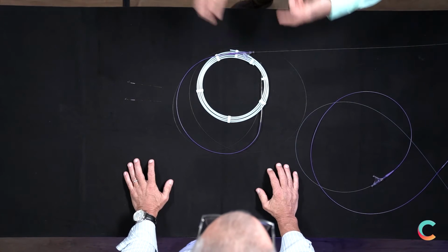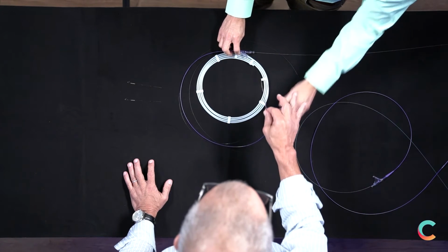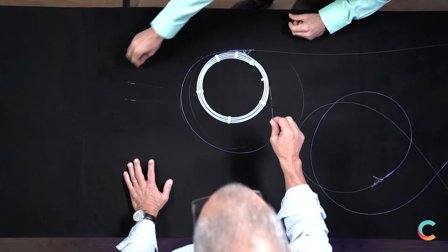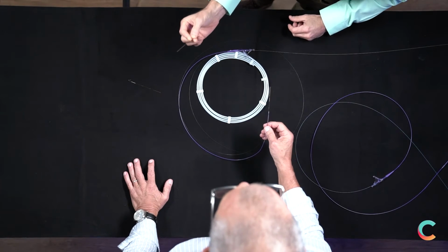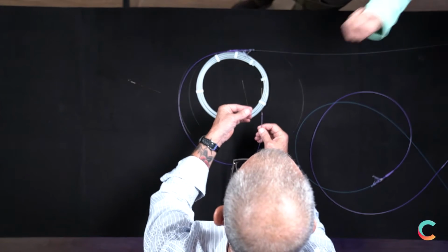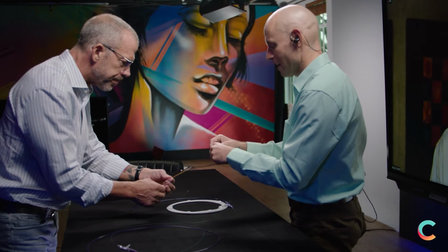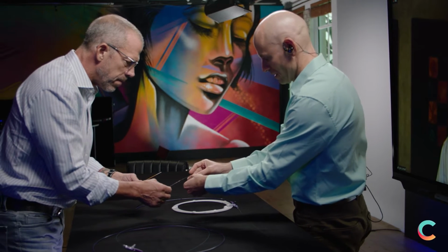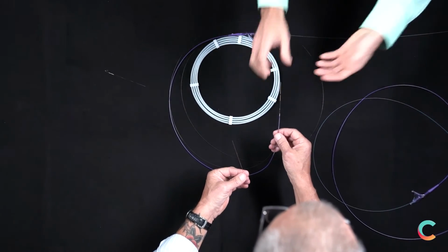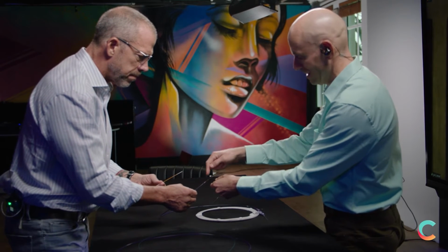Right. So as Gary and I were discussing, this is the base parent balloon catheter, right? And that's going to be common. Everybody's going to understand what that is. It's not really any different. But the idea is you can take these smaller adapters, and there's a unique way to couple the two things together so that it's one way, it's secure, it's reliable, it's robust, and it's not going to come apart. And now you've added a feature. In this case, it's a very simple feature. You've just added a secondary lumen so that now the physician can use 2 wires at the same time. One is through this rapid exchange, using rapid exchange techniques, but you still maintain the central lumen.